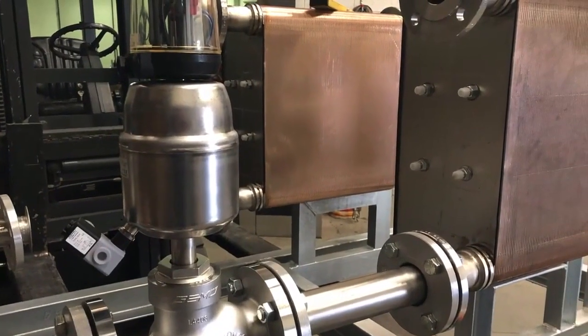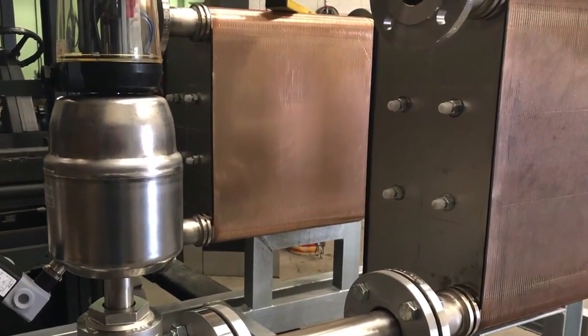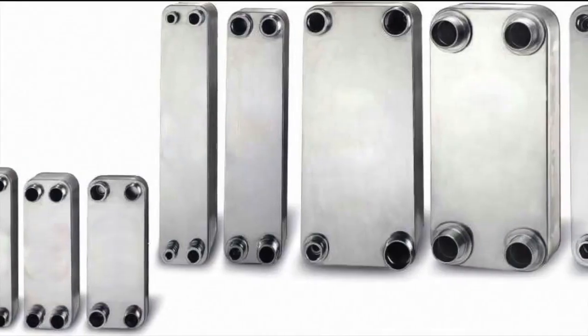Let's get to the initial point, nickel or copper. The technology started with copper heat exchangers, followed by the birth of nickel brazed heat exchangers. Why? Despite its excellence as a material, copper has compatibility limits that need to be considered, especially in certain applications, such as its ability to resist corrosion from specific substances. If, for instance, we use copper-brazed plate heat exchangers for steam and boiler water treated with amines, obviously ammonia, amines do not get along with copper. They corrode it, and in a short time the heat exchanger will start to leak.